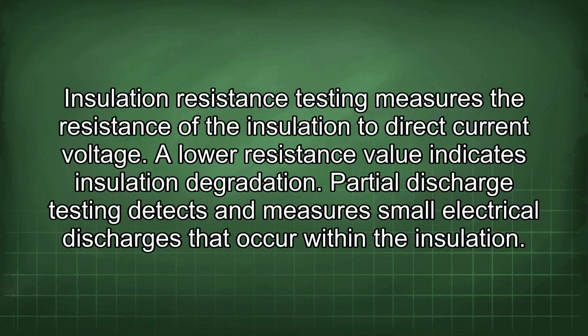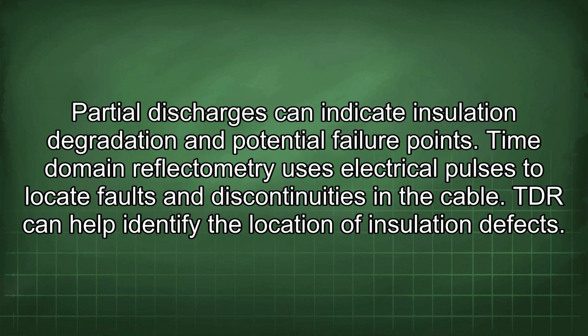Insulation resistance testing measures the resistance of the insulation to direct current voltage. A lower resistance value indicates insulation degradation. Partial discharge testing detects and measures small electrical discharges that occur within the insulation. Partial discharges can indicate insulation degradation and potential failure points. Time domain reflectometry uses electrical pulses to locate faults and discontinuities in the cable. TDR can help identify the location of insulation defects.